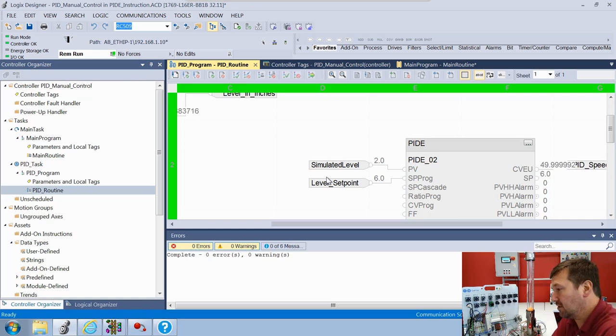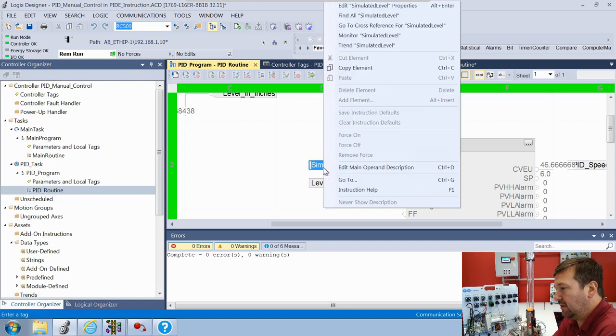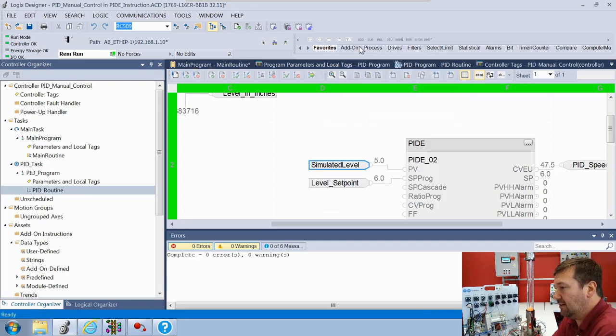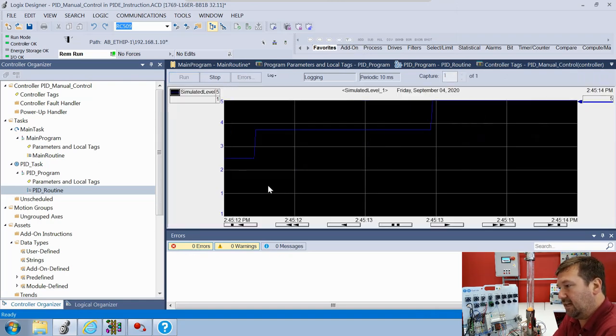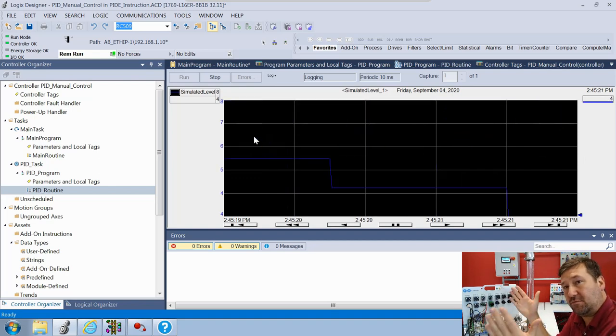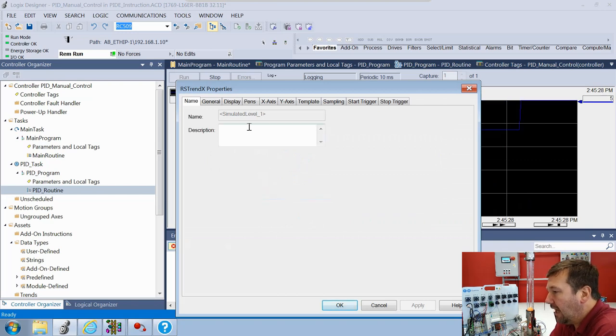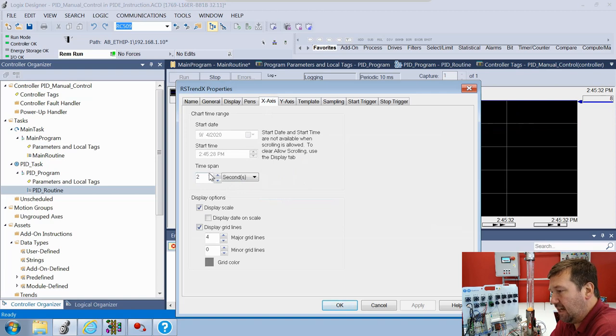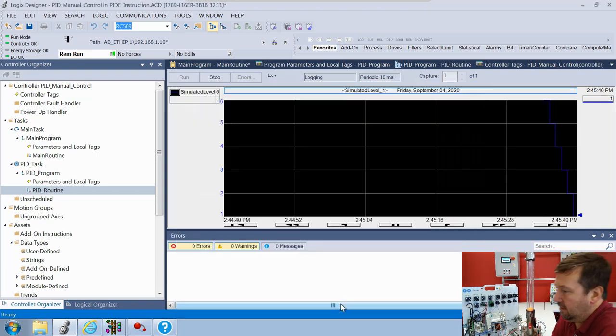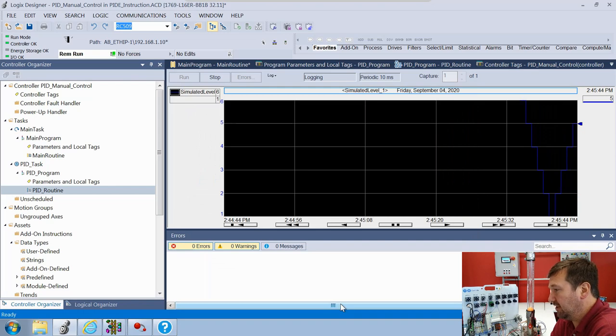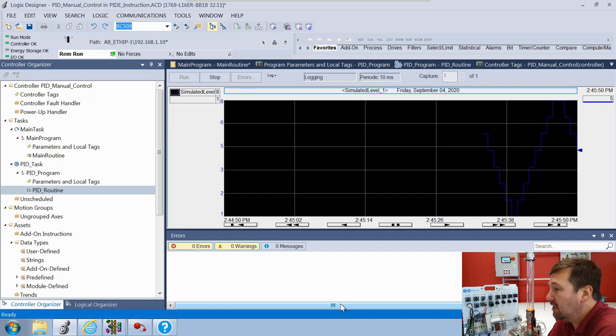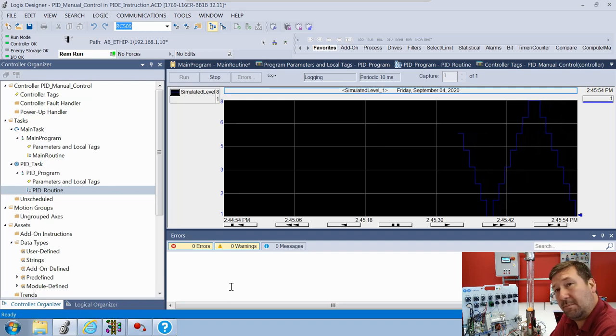I want to set up a trend so we can see visually what's going on. Right-click the simulated level and find 'trend simulated level'. You should see something that looks like an up-and-down stair step. The range is too small, so right-click and go to chart properties, then the x-axis, and change the time span from two seconds to one minute. Now we should see more of a stair step going up and down.